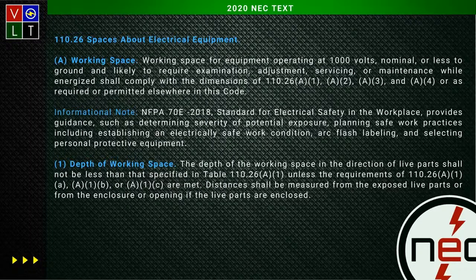Now, the interesting part here is I'm just dealing with working space, and at working space we're telling you to look at 70E. It'll talk about determining severity of potential exposure, planning safe work practices, including establishing electrically safe work condition, arc flash labeling, and selecting PPE. What I want to point out is it's one thing to have the clearance to work on something while it's energized, but this working space has nothing to do with the limited approach boundary, the restricted approach boundary, or the arc flash boundary. All four of those are separate entities.